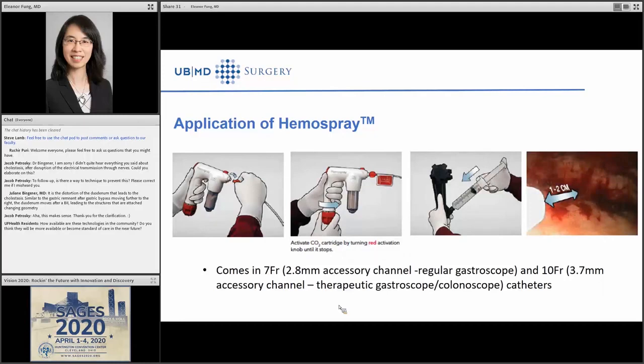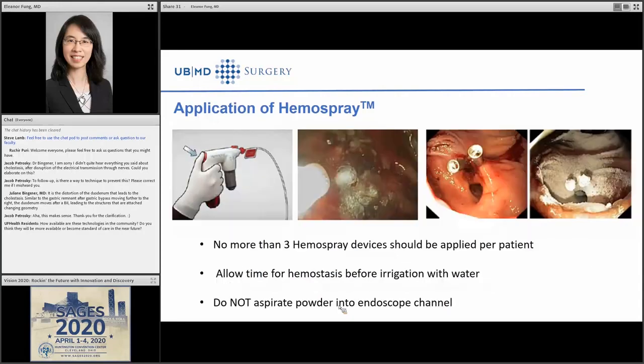You want to make sure the probe is 1 to 2 centimeters away from the tissue, as once that probe contacts the tissue, water can form on the end of the probe, which can block or cause occlusion so that the powder won't fire. So it's very important that it's not in direct contact with the tissue. When you fire it like a gun, it sprays out this powder over a wide surface area, which is why you don't need to be targeting a specific region.